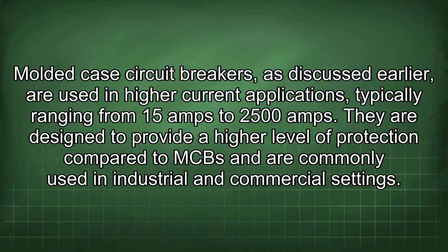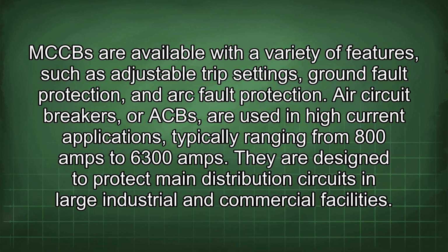amps. They are designed to provide a higher level of protection compared to MCBs and are commonly used in industrial and commercial settings. MCCBs are available with a variety of features, such as adjustable trip settings, ground fault protection, and arc fault protection. Air circuit breakers, or ACBs, are used in high current applications typically ranging from 800 amps to 6300 amps. They are designed to protect main distribution circuits in large industrial and commercial facilities.